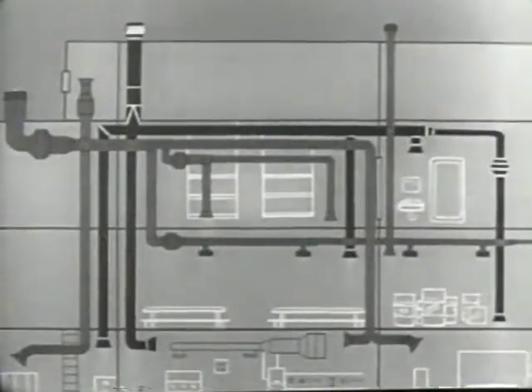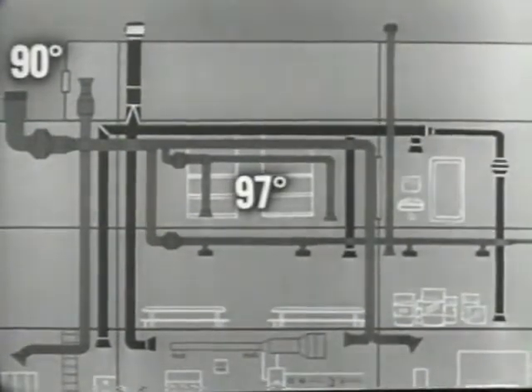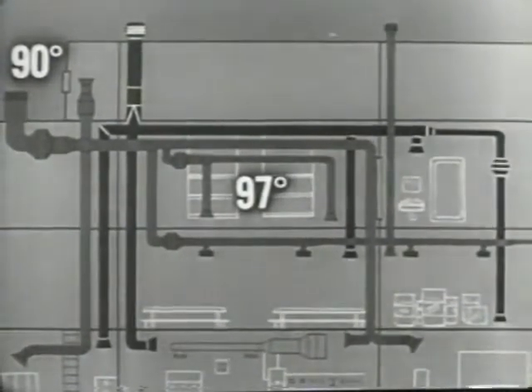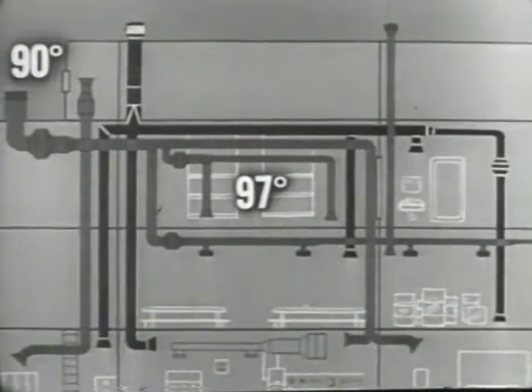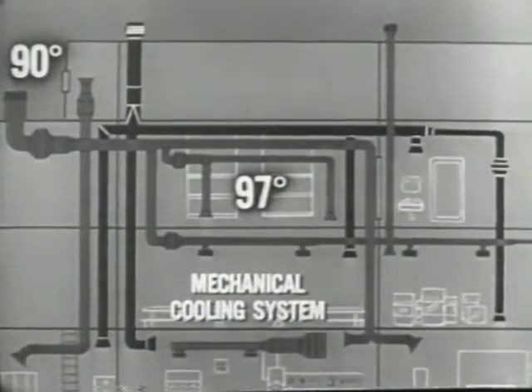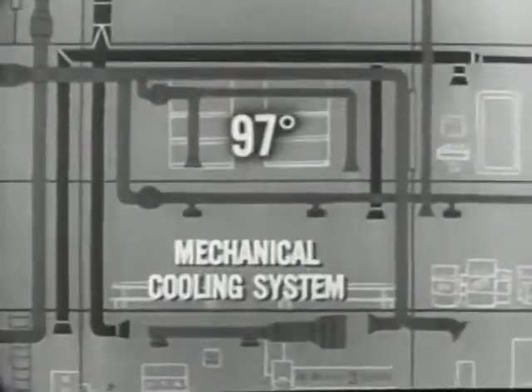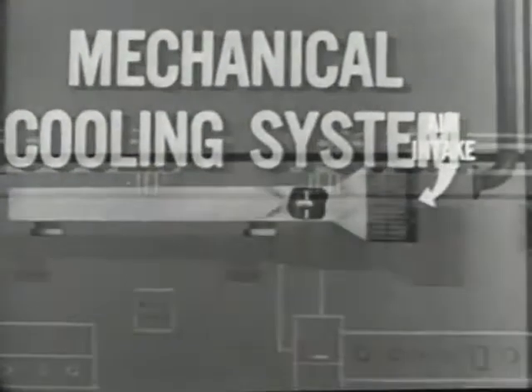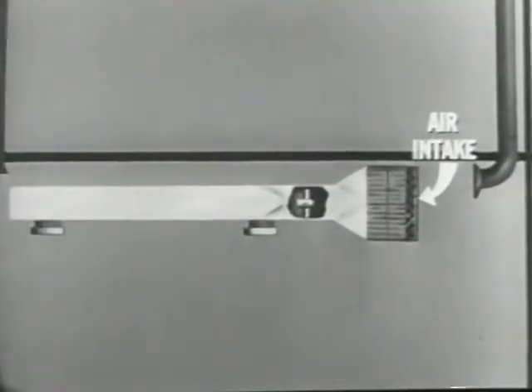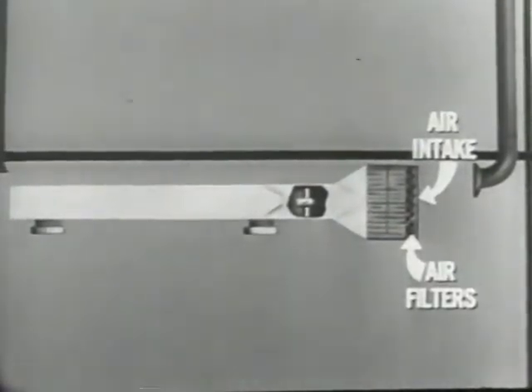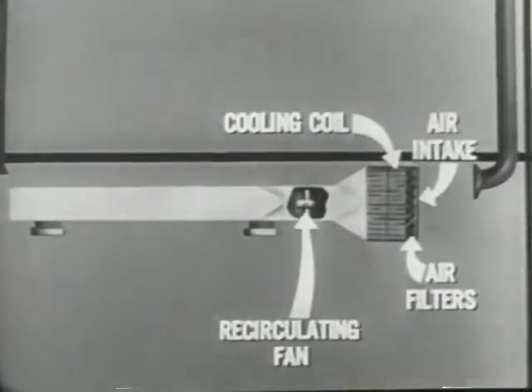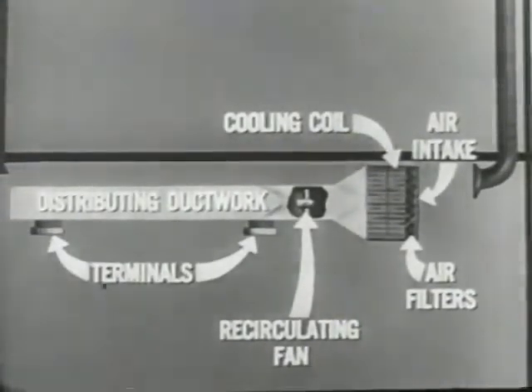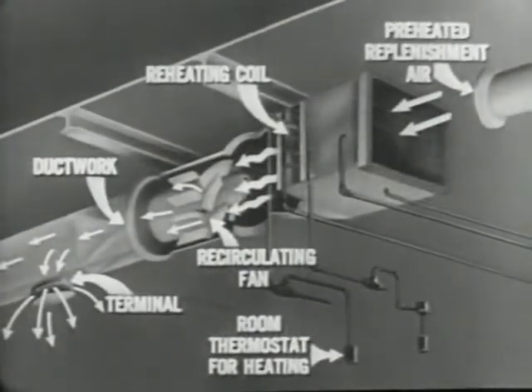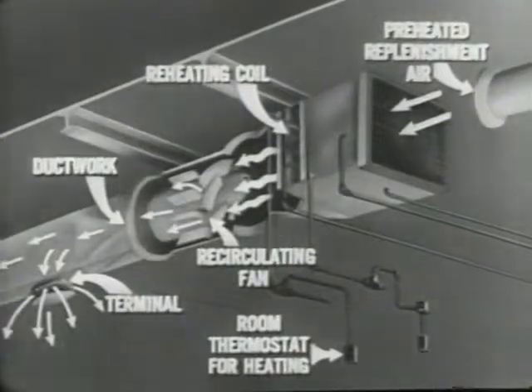We have seen how ventilation in itself cannot produce satisfactory space conditions with extremely high outside temperatures. It is therefore essential that a more effective means be used to cool vital spaces. This is accomplished by a mechanical cooling system which cools and recirculates the air. Its elements include an air intake, air filters, a cooling coil, a fan, distributing ductwork, and terminals. A reheat coil is also included for adding heat to the space in cold weather.